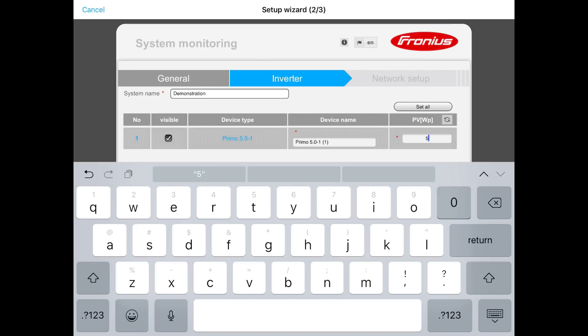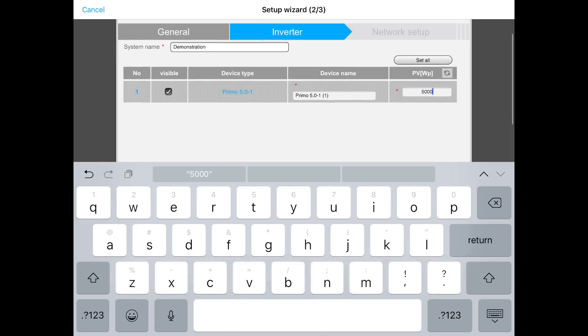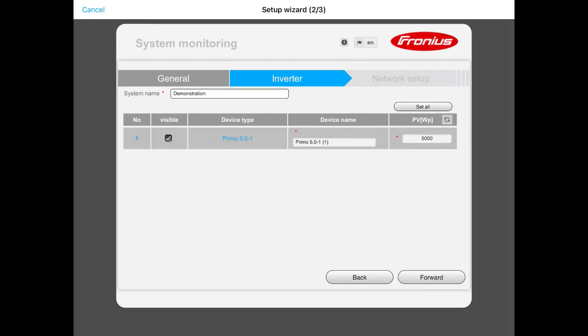Then we want to set the system time — that should already be set up correctly. Make sure the time zone settings are correct, then press forward. Now we get to put in the inverter information. It should automatically come up with the size of inverter and device type. What we want to put in is the kilowatts peak of solar panels — so if it's 5 kilowatts of panels, enter 5000 watts. Then press forward again.